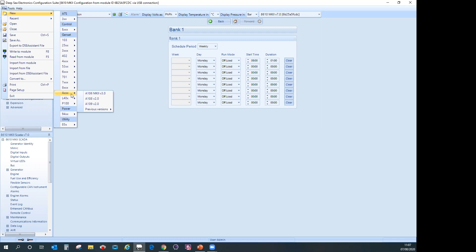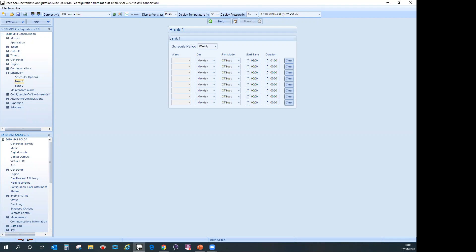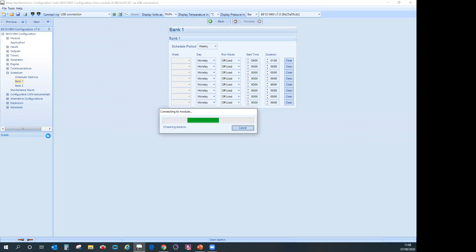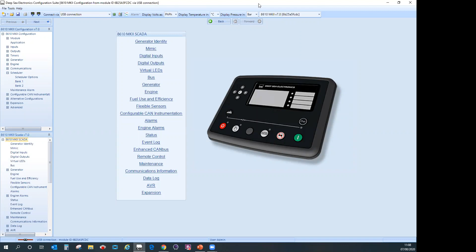So that's an example of just a small change you can do. Now, if you look down here, we can see in the SCADA section, the little link here has actually been broken. So every time you disconnect and reconnect your USB connection, that breaks and you have to manually reconnect it. That's just to reduce the load on the USB port when you write changes. So if you just click the up arrow and then click the down arrow, it will reconnect. And there's other reasons for that as well. It might be the case that you've connected to a number of controllers and you want to click the drop down here and select other controllers and then select the SCADA pages for that controller. So I've now changed my controller.